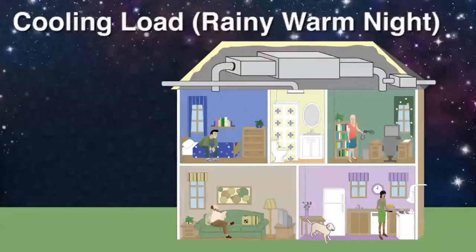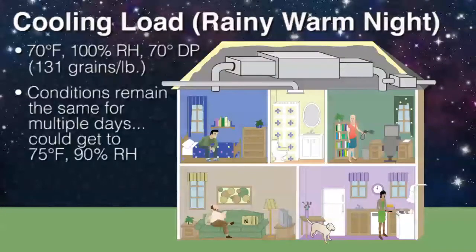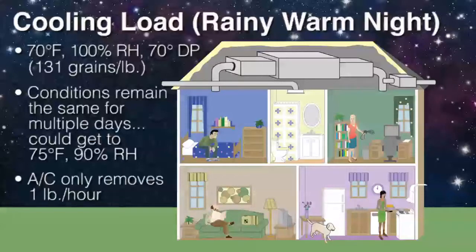Followed by a rainy night — worst case scenario — the moisture levels continue to rise. If this situation continues for several days, which it commonly does, we could easily reach 90% relative humidity in that home and be very uncomfortable. As the AC short cycles in this kind of condition, at best it may remove a pound of water per hour. All of our infiltration and loads here are based on 100 cubic feet of fresh air infiltration plus occupancy of four, which may or may not be the case depending on how the home is utilized.